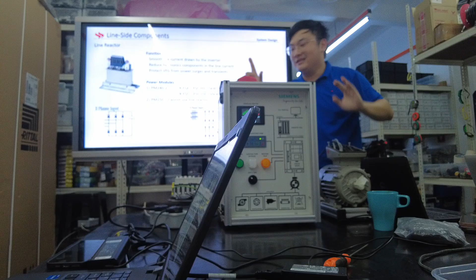Tapi kalau you ada power monitor, you akan nampak you punya voltage naik turun balik. Itu transient current, okay, so that one will also affect your inverter. So usually this is like to protect only lah, protect the surge and the transient, but the voltage peak is still going to pick up. Imagine it's just a transformer, cannot do much. There's no control, this is a passive line filter.